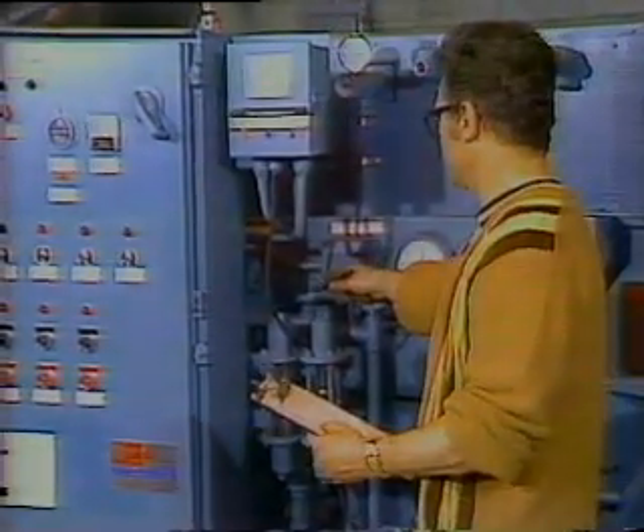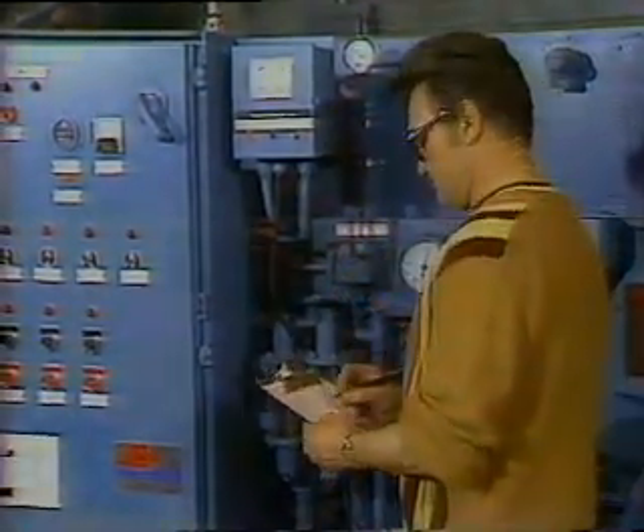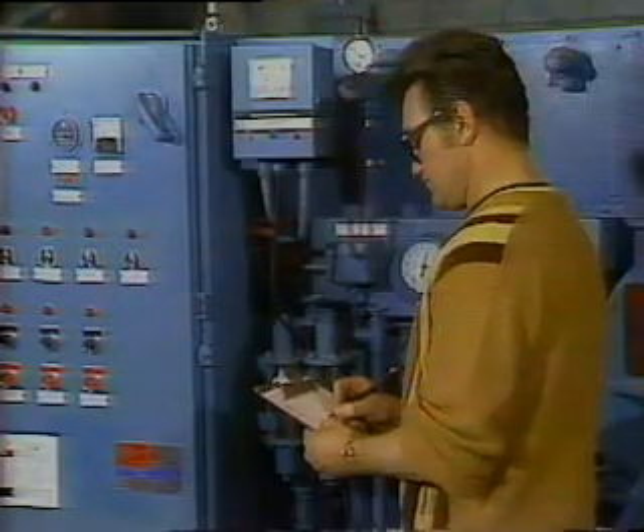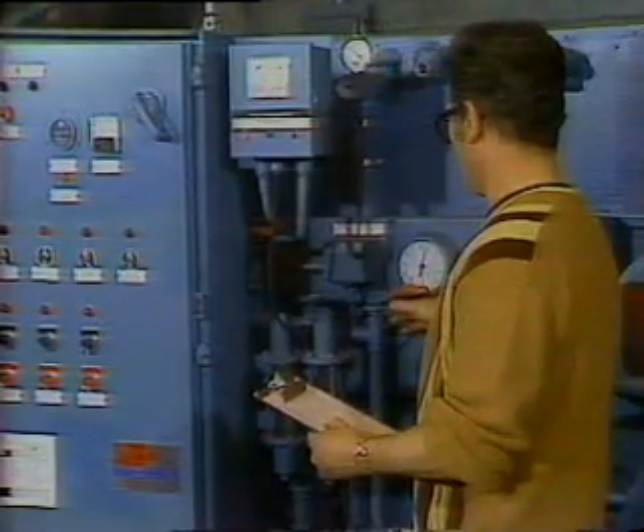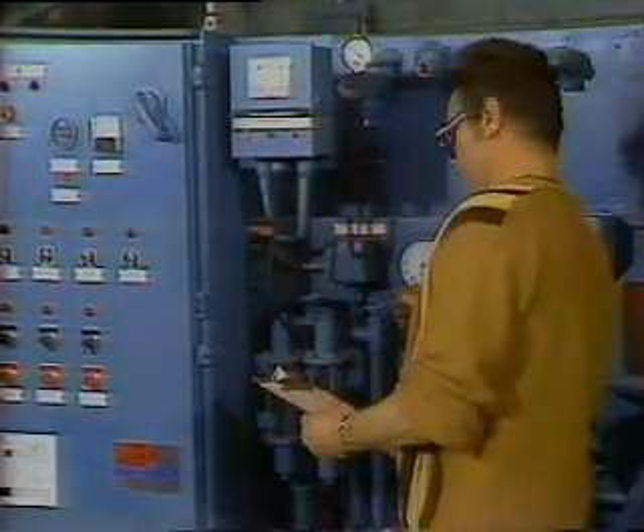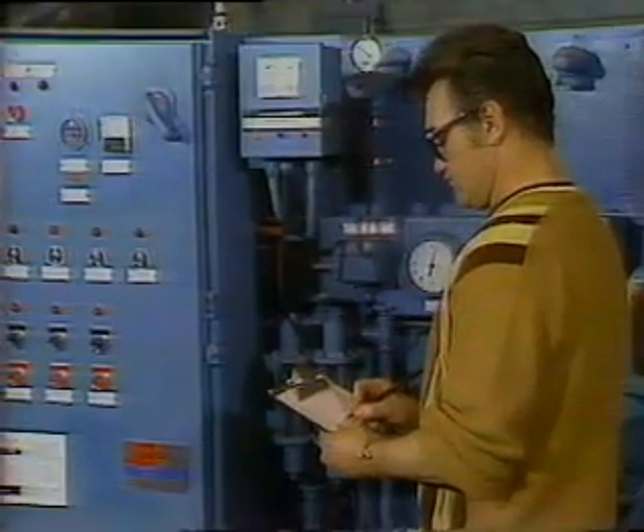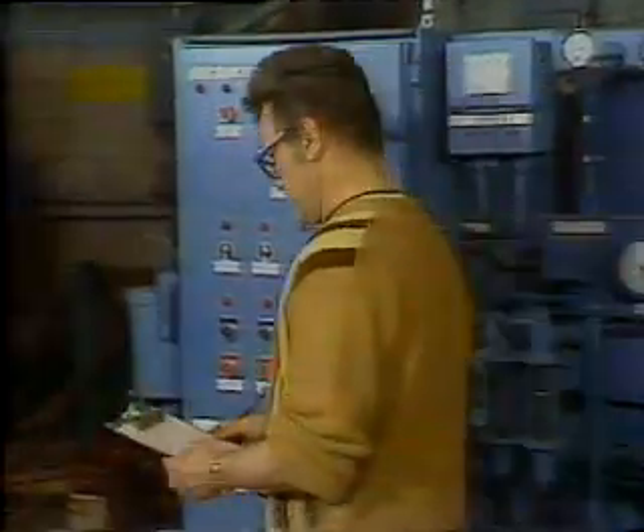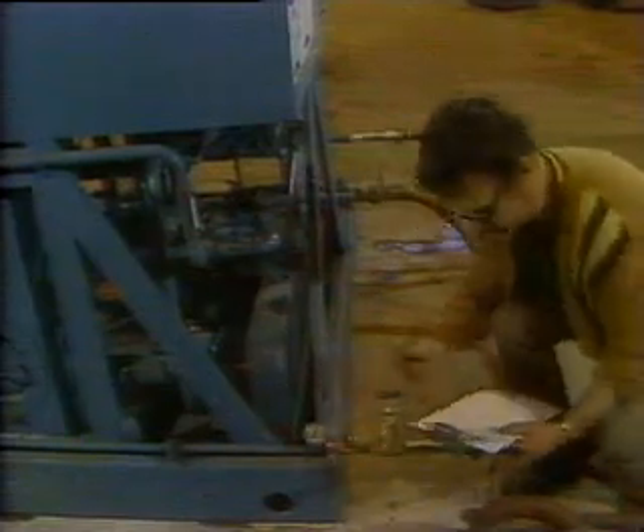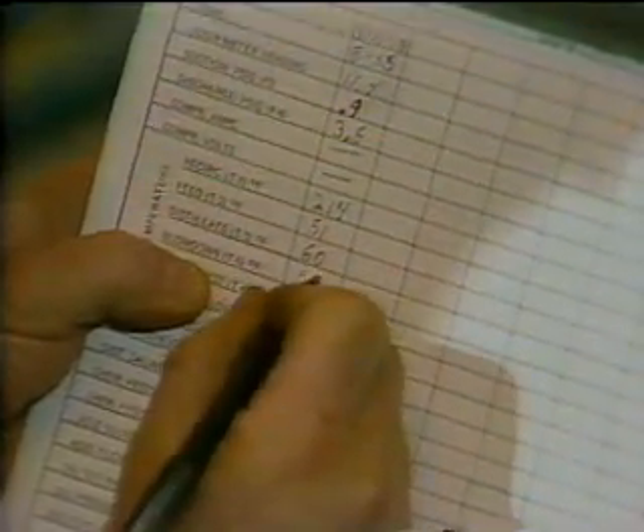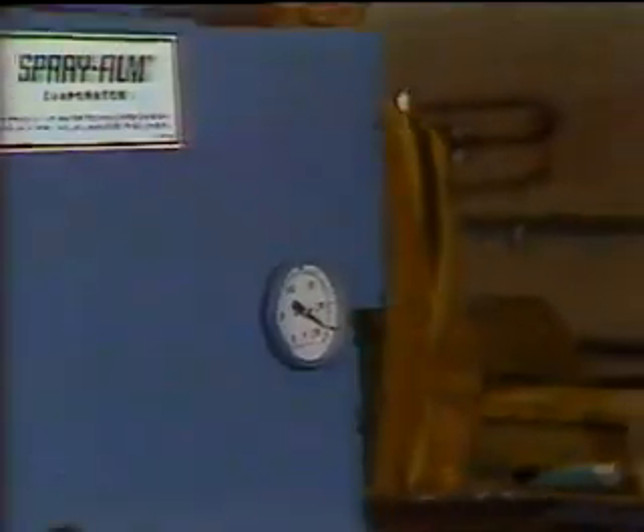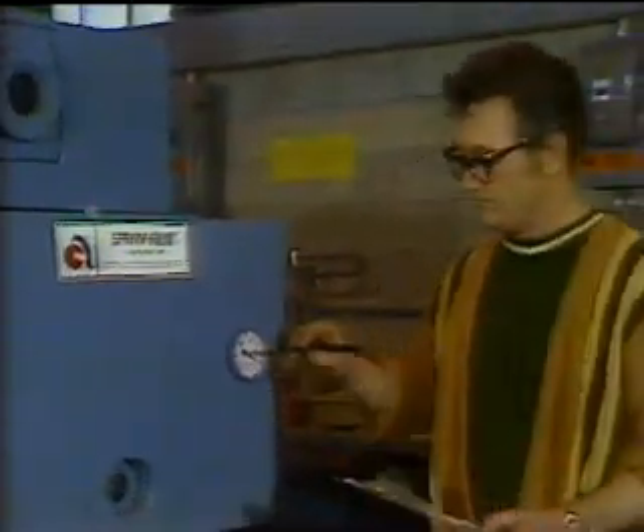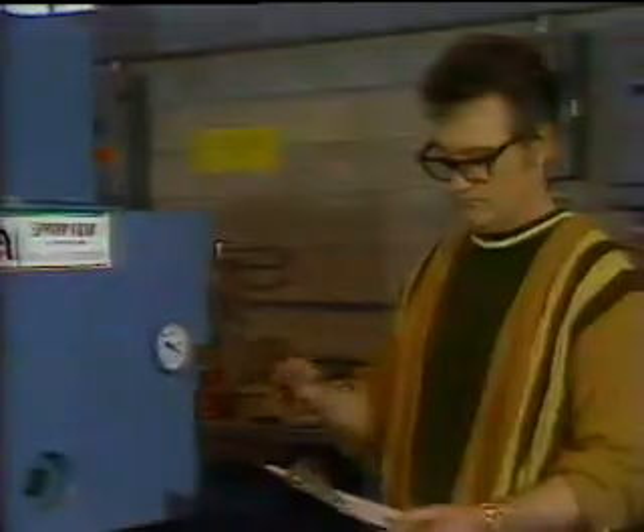Feed water and distillate temperatures are next. The distillate will normally leave the heat exchanger at about 12 degrees Fahrenheit higher than the incoming feed water. And again, if it rises much above that, like 15 to 18 degrees Fahrenheit, it indicates that the heat exchanger is full of scale, and both the feed water and blowdown sides need to be cleaned. Blowdown temperature goes here. Steam chest temperature is read here.